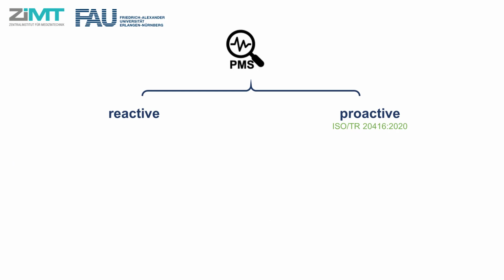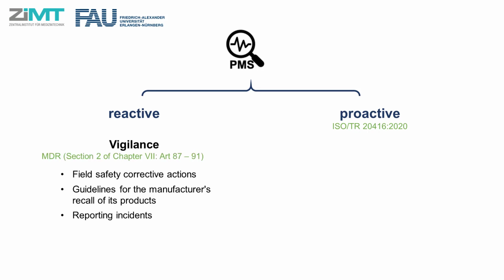Post-market surveillance systems are usually divided in two big sections, reactive and proactive. Part of the reactive section of the post-market surveillance system is vigilance. It requires that a manufacturer take actions, called field safety corrective actions, when serious accidents occur on the market, and it describes in which case the manufacturer shall recall its products. Section 2 of Chapter 7 of the MDR obliges the manufacturer to report incidents to the relevant competent authorities. It describes how to submit those reports, and it requires the manufacturer to analyze their vigilance data.